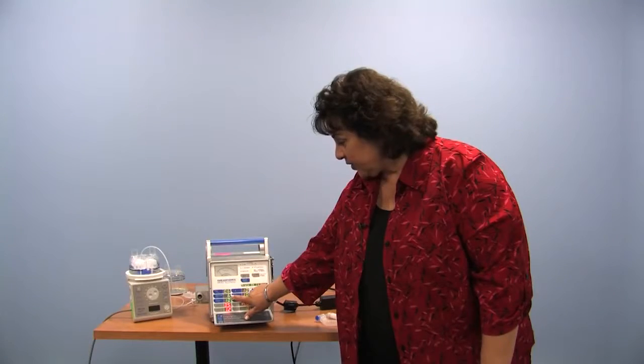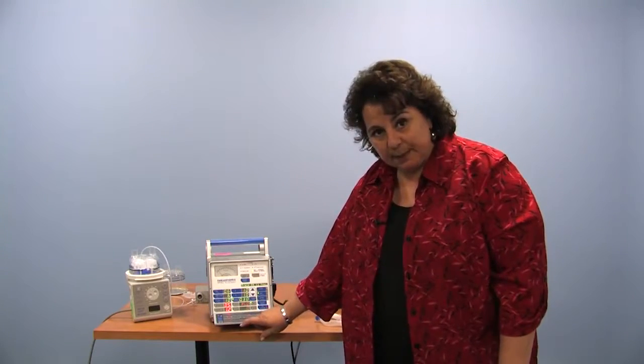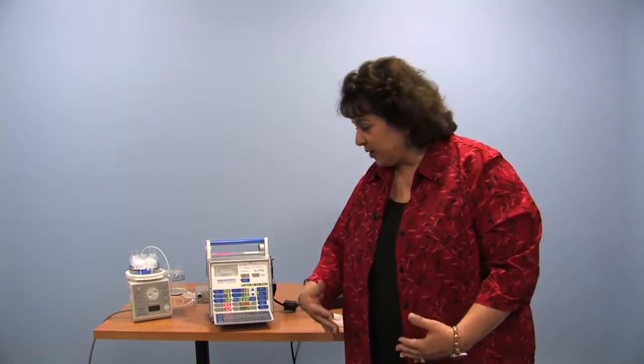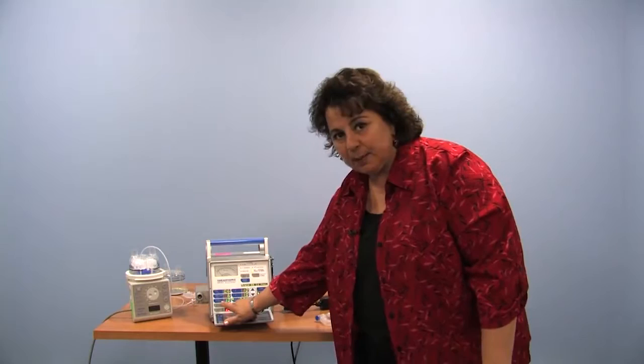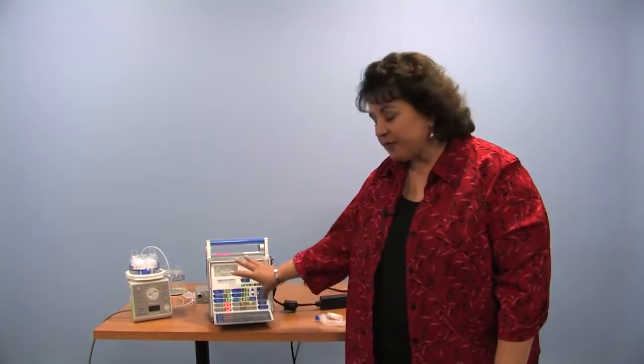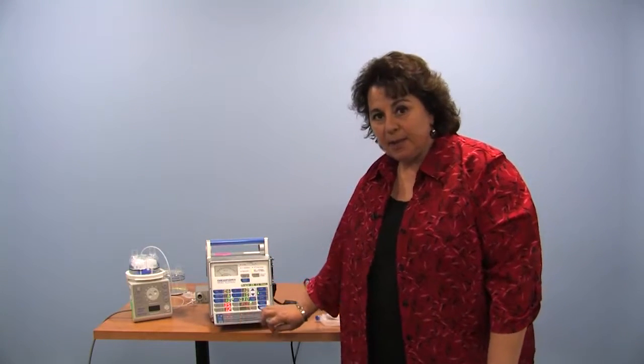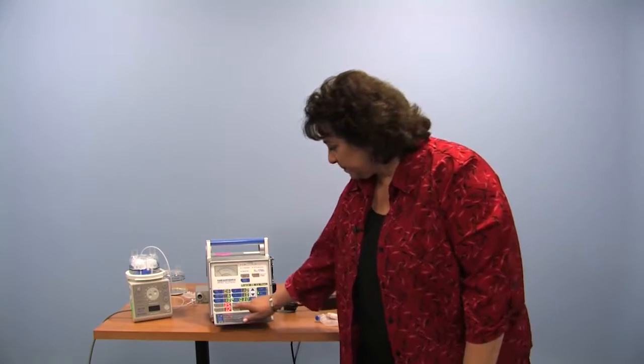Right now you see it set on 6 centimeters of water. This machine refers to PEEP or CPAP, which is the end exhale pressure to help keep the lungs open between the breath cycles. It calls it P base. So in some of the reference areas you'll see P base, meaning baseline pressure.